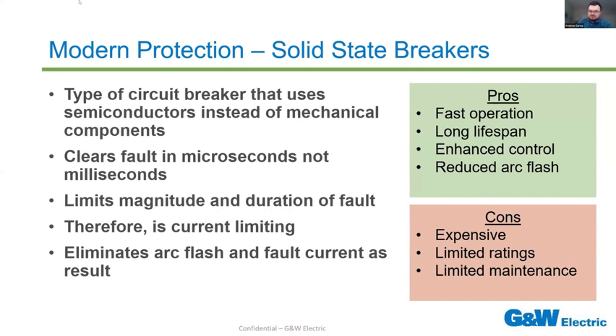However, things often sound too good to be true, and they are, and there are some pretty big cons with these devices as well. The biggest one being that they're very expensive at this point. They're expected to reduce in cost, but they're still going to be a lot more expensive than a traditional circuit breaker. There are limited ratings options currently available. The higher ratings you go, not only are there less available options, but the price and size of these breakers increase pretty dramatically. There's also limited maintenance options for these devices. If something goes wrong inside one of these devices, you could be on the hook for replacing a significant component or portion of these or the entire thing. There's no nuts and bolts in here that you could adjust to try and fix it. When it's busted, it is busted.